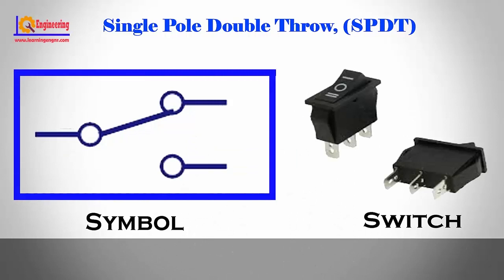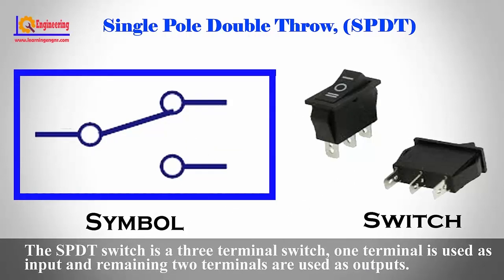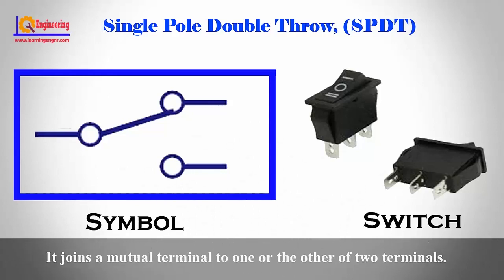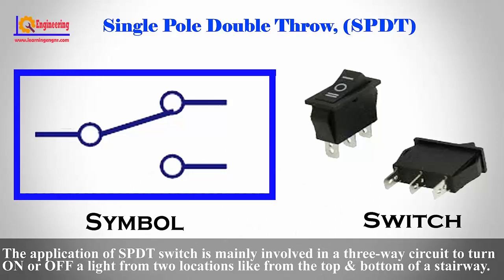SPDT — Single pole double throw. The SPDT switch is a three terminal switch. One terminal is used as input and the remaining two terminals are used as outputs. It joins a common terminal to one or the other of the two terminals. The application of the SPDT switch is mainly in a three-way circuit to turn on or off a light from two locations, like from the top and bottom for a stairway.